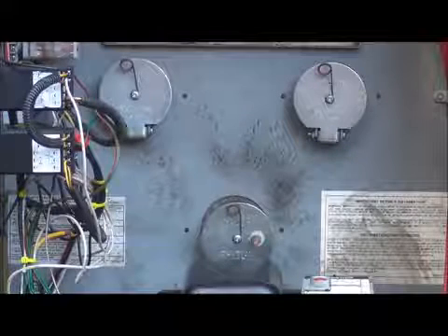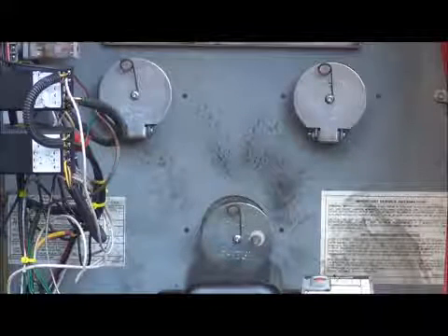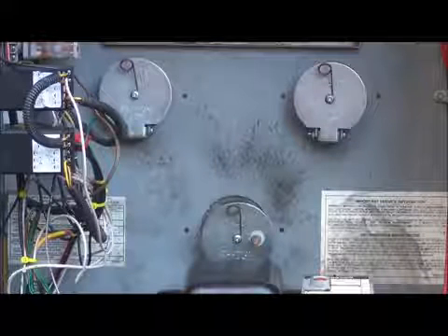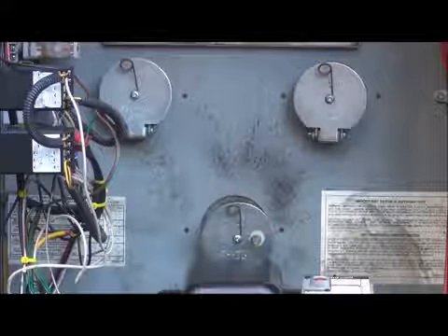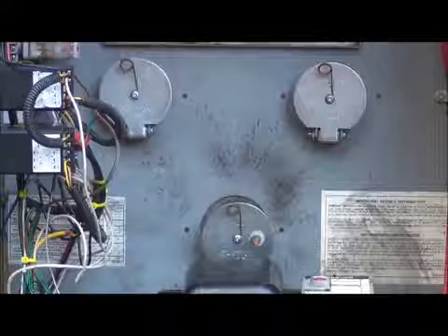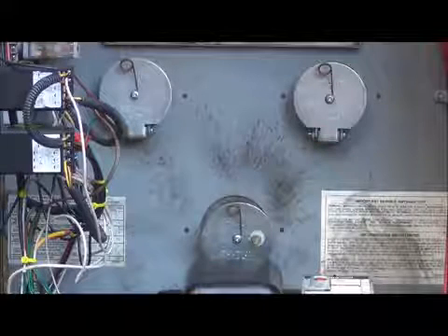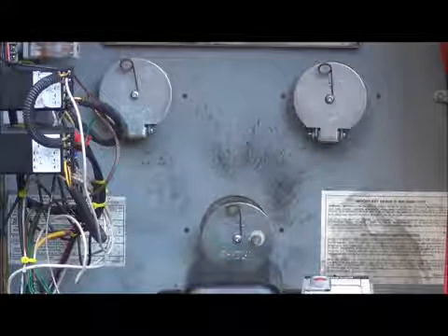This heat exchanger has some pretty good inspection ports. We can open it up and actually see what the flame looks like inside. I've adjusted it for a good clean burn, and the flame is about equal to the way that it was when it was still set up from the factory.